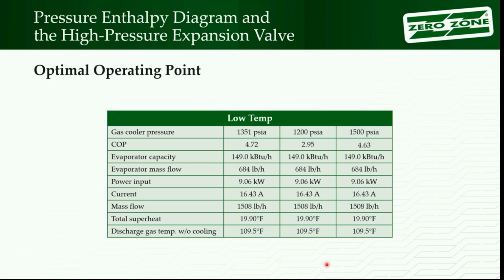And things would change if you raise the pressure up on that. Your discharge temperature is not going to be 100. It's going to go up above 100. So in a real system, everything's moving around, right? I'm on paper here. It's not happening. You don't see all those interactions going on.